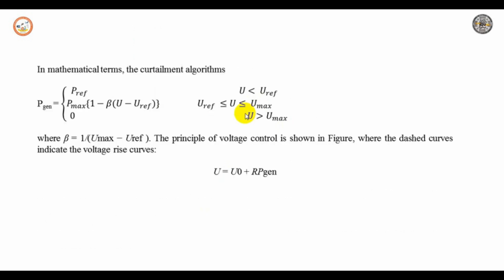So here the power generation equation can be given by P generation is equal to P reference, or P max times (1 minus beta times (U minus U reference)), or 0. There are limits to the reference: where U is less than U reference, where U is between U reference and U maximum, or where U is greater than U maximum, where beta is equal to 1 divided by (U max minus U reference).